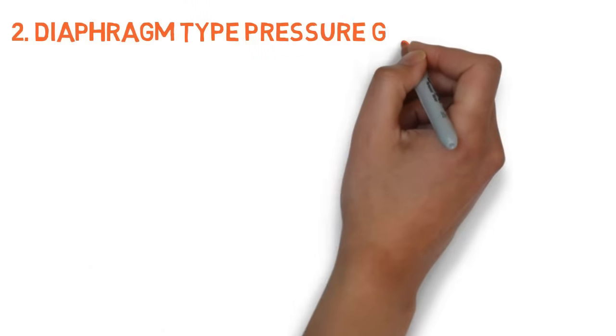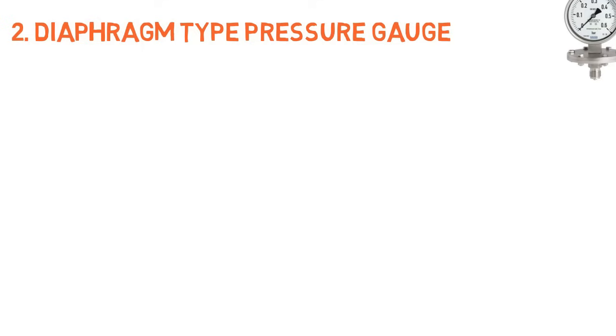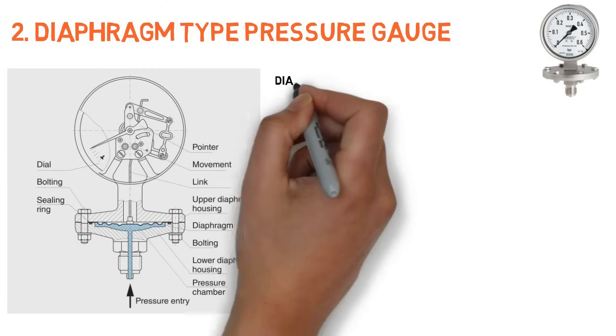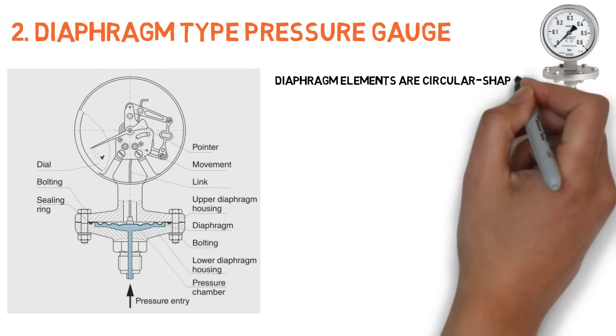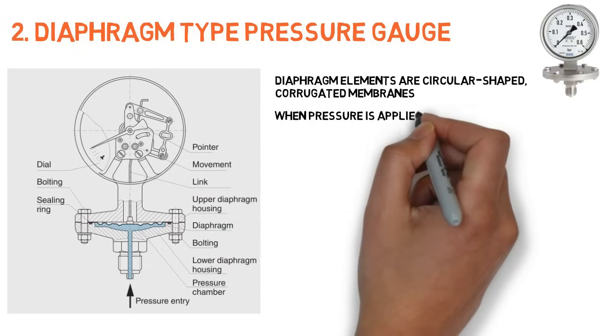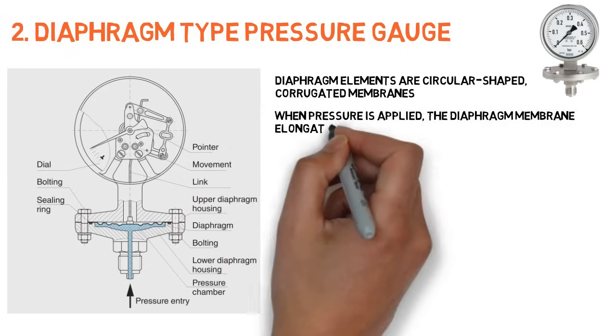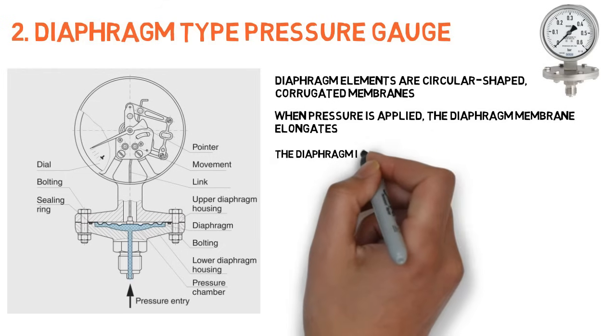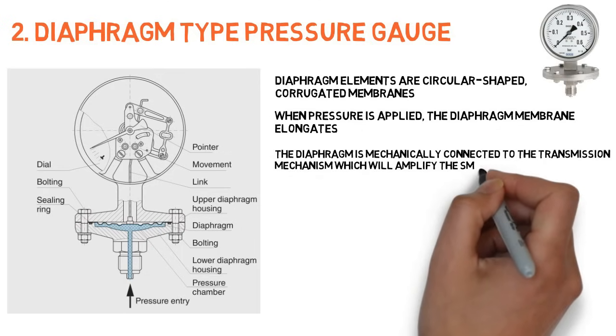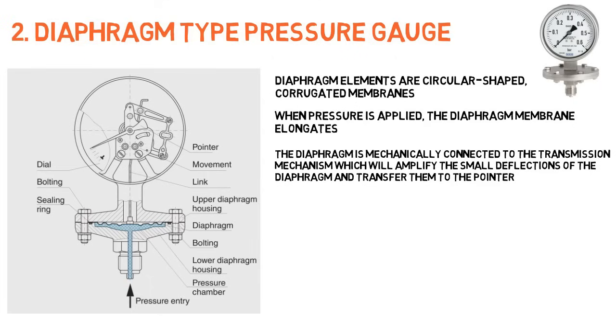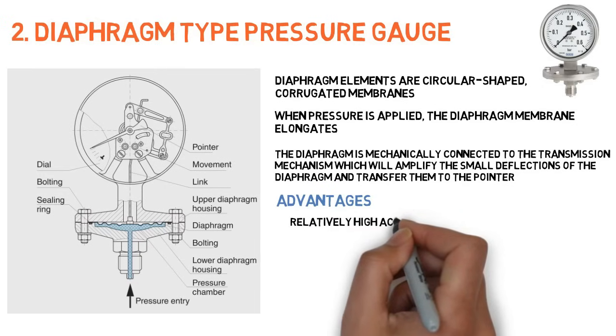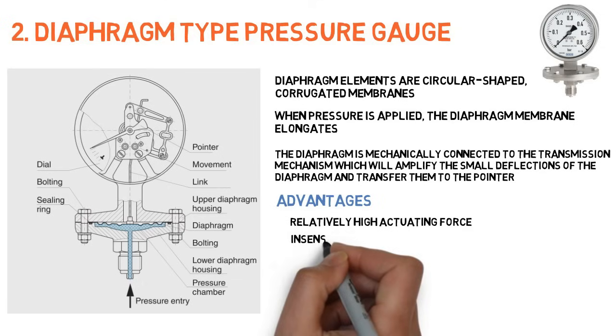Diaphragm type pressure gauge. Diaphragm elements are circular shaped corrugated membranes. When pressure is applied, the diaphragm membrane elongates. The diaphragm is mechanically connected to the transmission mechanism, which amplifies the small deflections of the diaphragm and transfers them to the pointer. In comparison with Bourdon tubes, these diaphragm elements have a relatively high actuating force and they are insensitive to vibration.